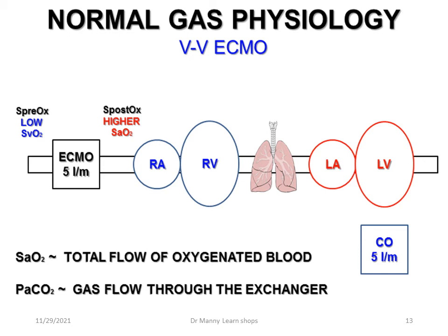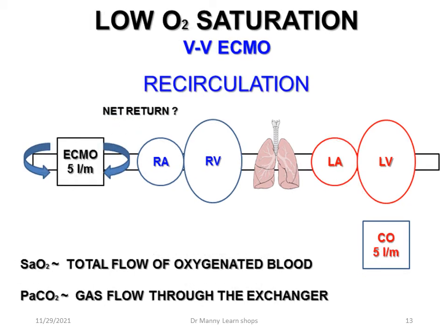So the SaO2 is determined by the total flow of oxygenated blood, and the PaCO2 is determined by the gas flow through the exchanger. Low saturation is caused by, first of all, recirculation, meaning that blood which has been saturated is being sucked back into the cannula which is accessing it. So there's mixing. The cardiac output is basically the same. The ECMO output is basically the same. It's approximately 5 litres per minute in combination.